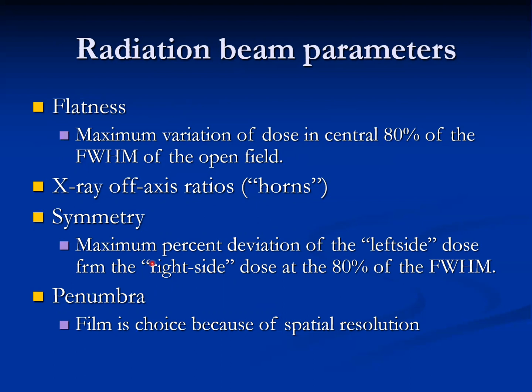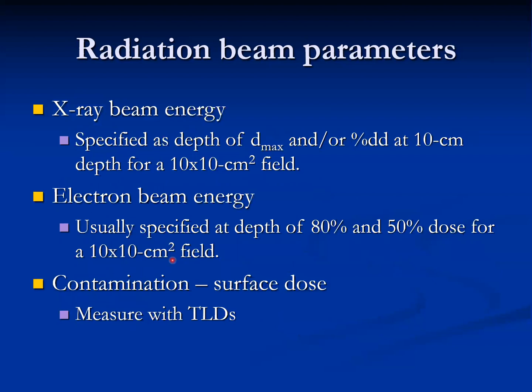You also have to calculate the penumbra. Film is a good choice because of its spatial resolution, but it can also be done with high-resolution chambers or a diode. For X-ray beam energies, specified at the depth of Dmax, percent depth dose at 10 cm depth for a 10×10 cm field. Electron beam energy is usually specified at the depth of 80% and 50% of the dose for a 10×10 or 15×15 cm field size, depending on the chosen energy.